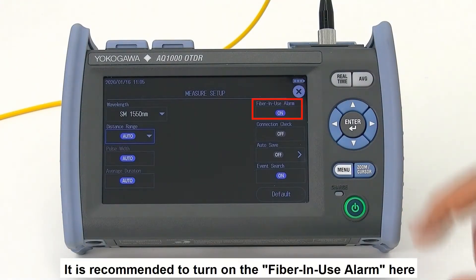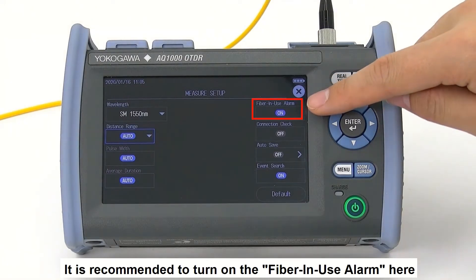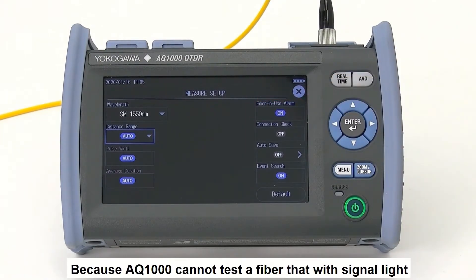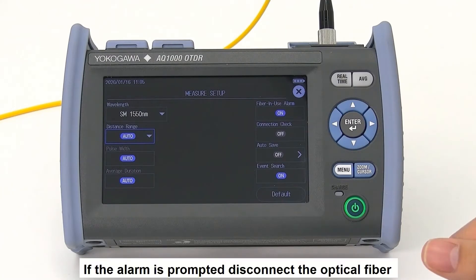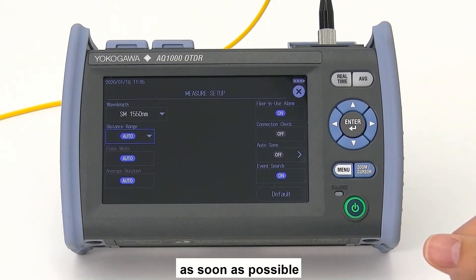It is recommended to turn on the fiber in use alarm here, because AQ1000 cannot test a fiber with signal light. If the alarm is prompted, disconnect the fiber as soon as possible.